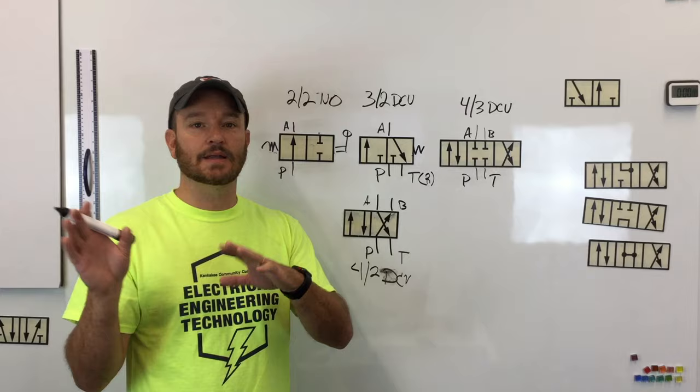After that, you just need to identify what the actuators are. This symbol here is a solenoid. This valve would be identified as a four-two directional control valve, solenoid control, spring return. If it had two solenoids, it would be a four-two directional control valve, double solenoid. With no spring present, there is no true normal position — the valve stays in its last position. This one here would be a lever-actuated, spring-return, normally open two-two directional control valve.